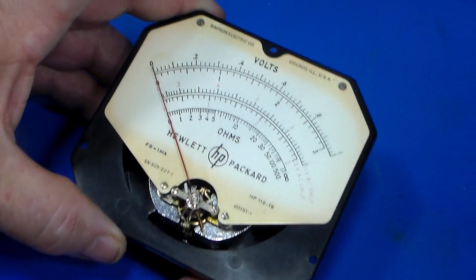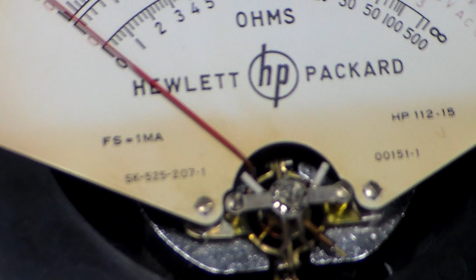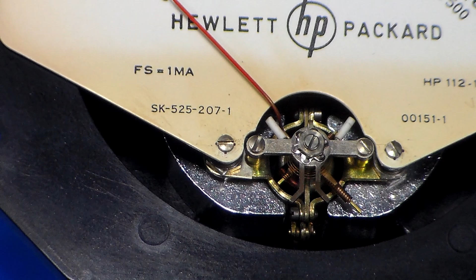But now what we have is the actual meter movement, and we'll just zoom in a little bit to get that to focus. It was fairly difficult for me to actually see down here because I had a fair bit of strong light trying to look down along the meter magnet, the curved section where the coil goes around. Now I'll just carefully do this, you can see the coil as it moves, and what I suspected was that, and I could actually see a small amount of corrosion in the area, little spots of corrosion. Those I thought were maybe just intermittently fouling on the meter coil as it moved, particularly with a low momentum coming up here, that it was causing it to stick.